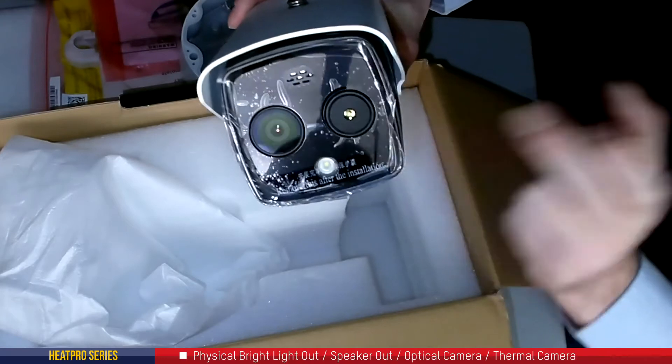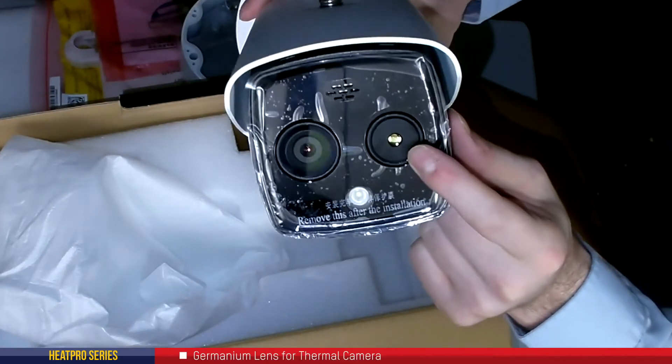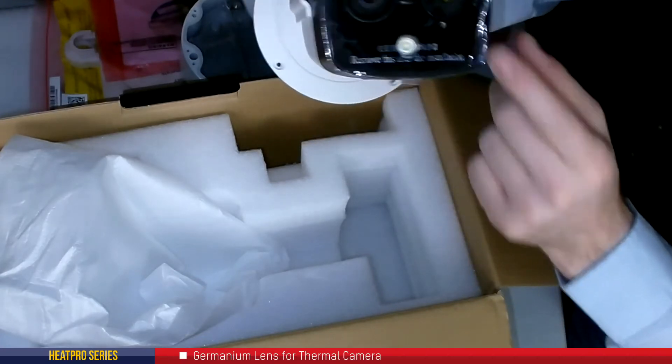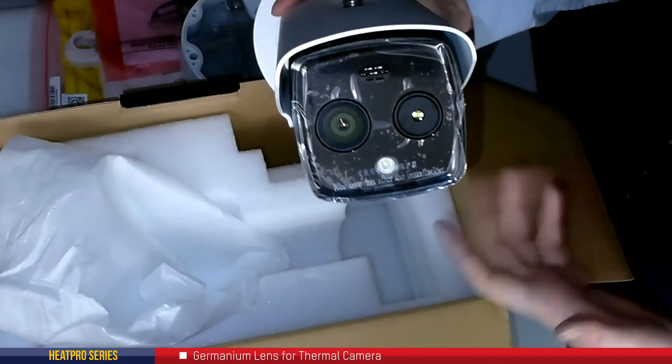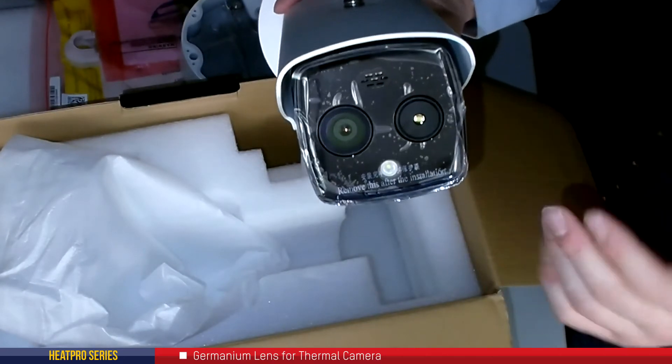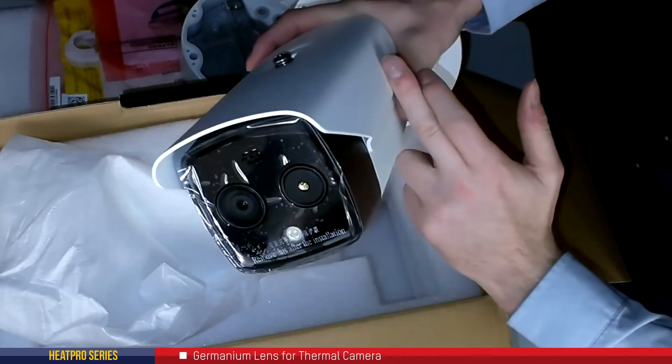Now the thermal camera has a different lens and sensor compared to the optical. This uses what's called a germanium lens, almost like a piece of metal, and that is what's going to reflect the visible light spectrum and therefore only allow the infrared radiation to penetrate through that lens and hit the image sensor in the back.